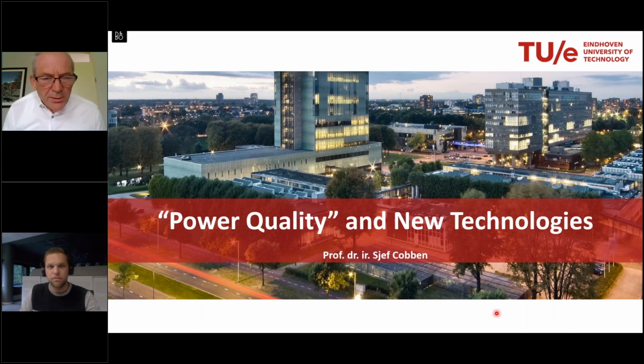No, I think it is. This transformer will give you a large increase in the possible voltage variation in the low voltage network. Normally you have to calculate with plus or minus 5%, maybe plus or minus 6%, taking into account the variation in the medium voltage level. So it gives you at least an increase in the possible voltage variation, even when you have load and production on different feeders.